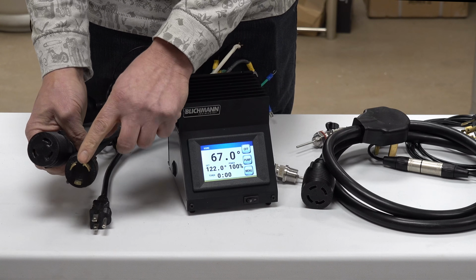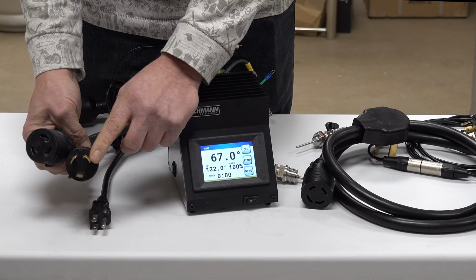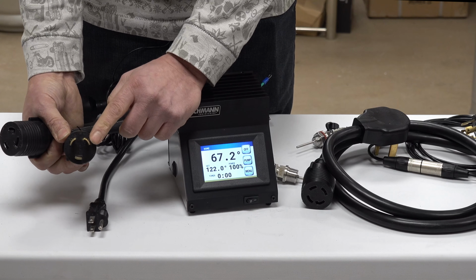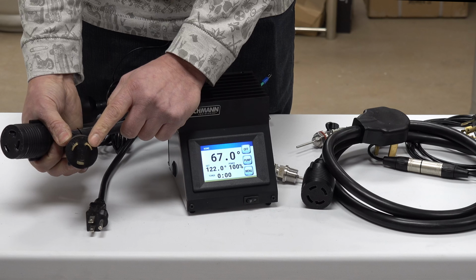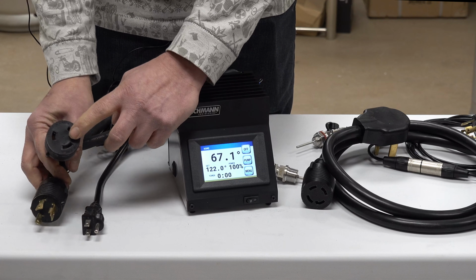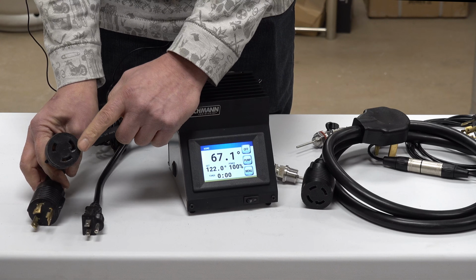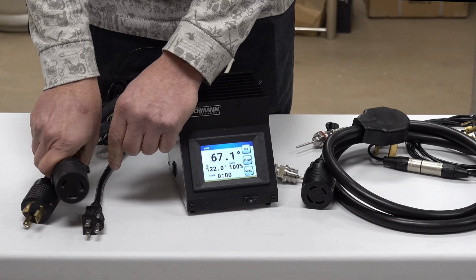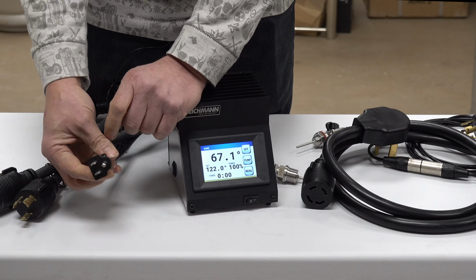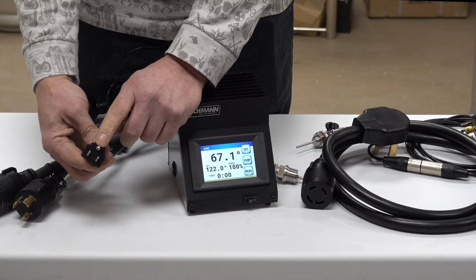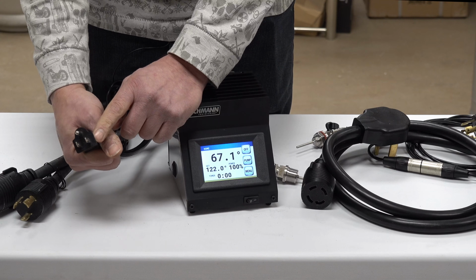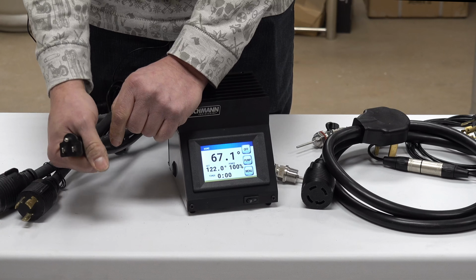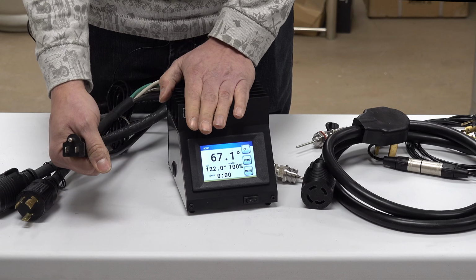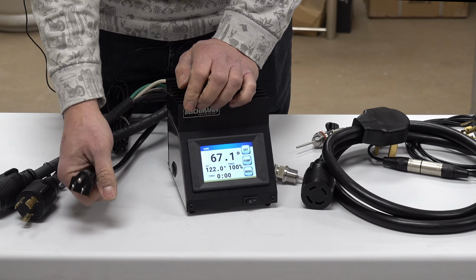You have an L6-30P male plug, which is the 240 volt input into the controller. You have an L6-30R, which is the element output of the controller. And then you have a NEMA 5-15P. This is a typical male plug of a 120 volt circuit. This supplies the controller with power just for the pump output.